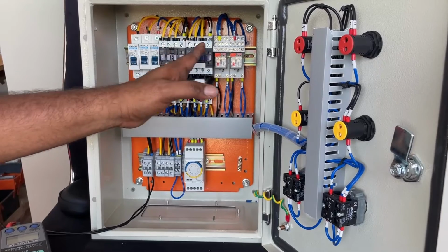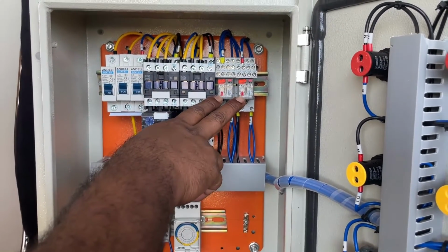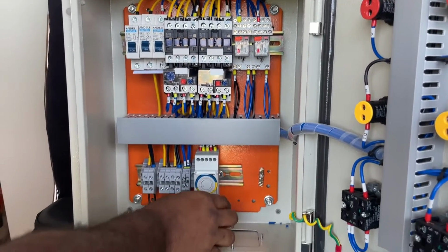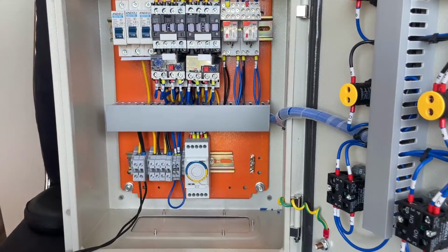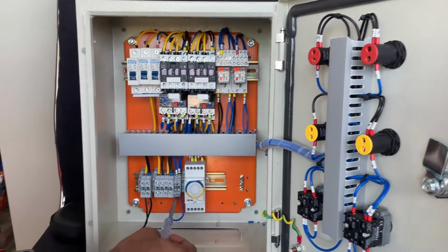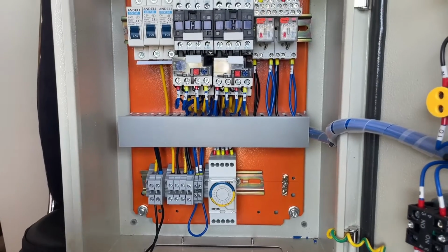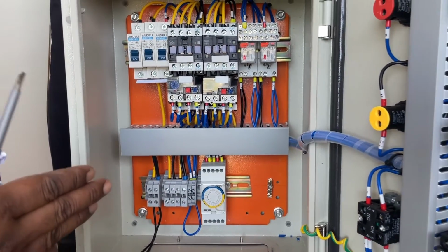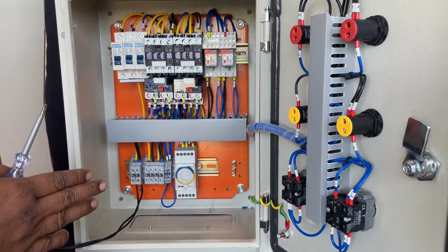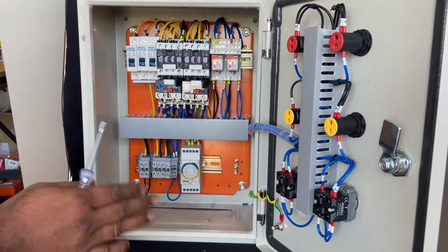And this is for the second fan, and we have 2 relays. I will tell you the purpose of these relays, and also the main component. This is an analog 24-hour timer. The important thing is we have provided the fire interlock provision. Once the fire alarm is activated or the fire is engaged in the working area, this fan will automatically shut off. So this is how we designed this panel.